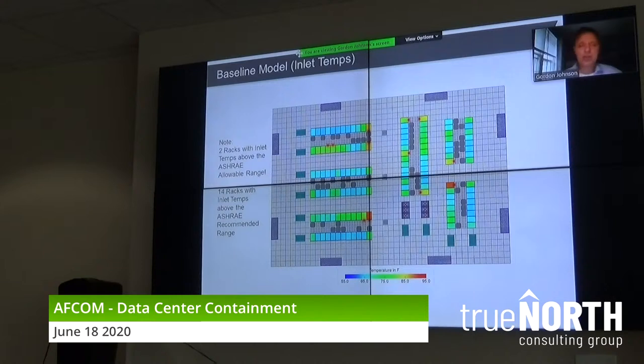So 14 racks above ASHRAE's recommended range. We don't like that because that's 24/7. Notice the note, two racks have temperatures above ASHRAE's allowable range. That's not good. And here's my problem. All of my CRAH units are running at 100% fan speed. I guess I could lower the temperature from 62 maybe to 55. That's going to make my energy bill go that much higher. It's not going to solve all my problems.